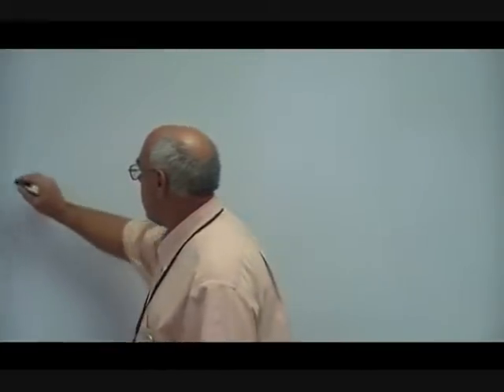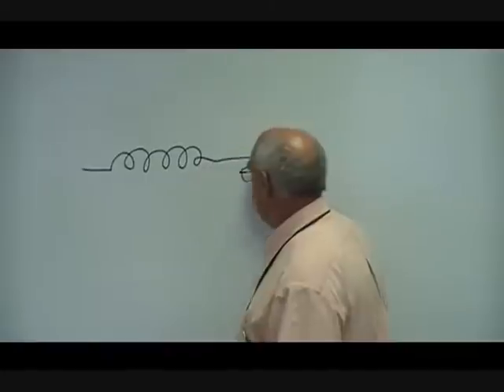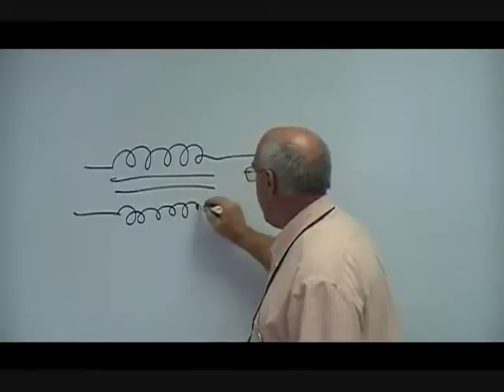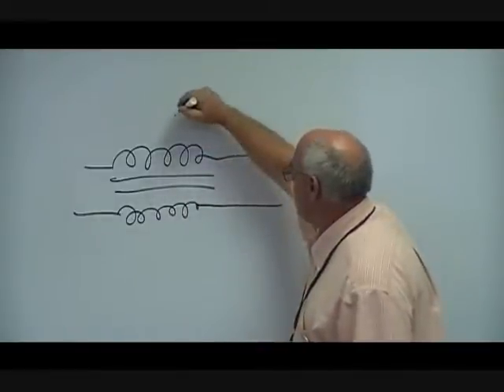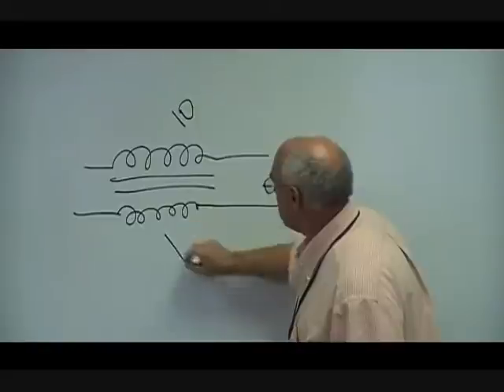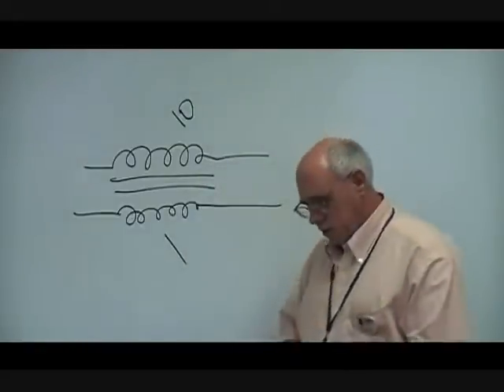Have you ever wondered how a transformer can have high voltage coming in and low voltage coming out, or vice versa? The transformer doesn't determine whether it steps up or steps down voltage — that's determined by how you hook it up. It's a turn-to-turn ratio. If we look at the symbol, if one side has 10 times as many turns as the other, that's a one-to-ten ratio.